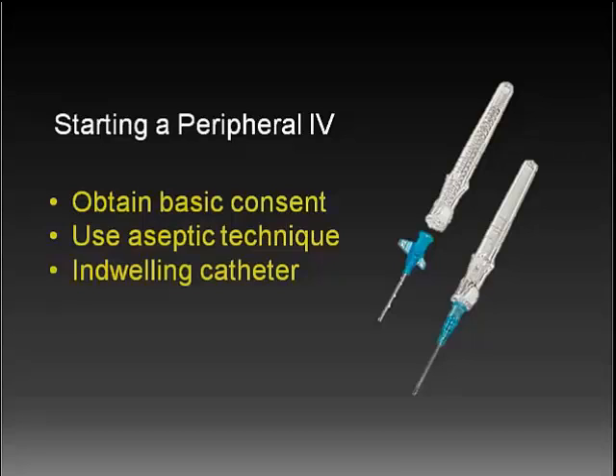An indwelling catheter set with a flexible plastic cannula should be used whenever a mechanical injector will be used for contrast media injection. The use of metal needles, such as a butterfly, should be avoided in conjunction with mechanical power injectors as they may contribute to contrast media extravasation and patient injury. Whenever possible, catheters and ancillary components in the contrast fluid path should be specifically designed for the pressure and flow rate capability with the parameters that will be programmed for the power injection. An indwelling catheter set typically consists of a plastic catheter and hub, a beveled needle and hub, a beveled position indicator, and a flashback visualization chamber.